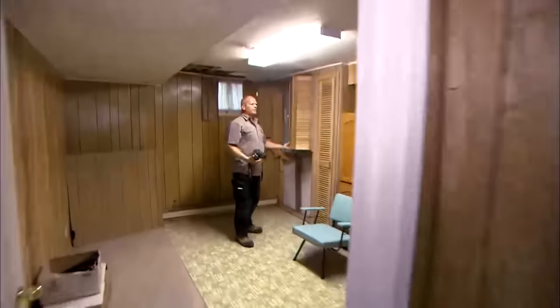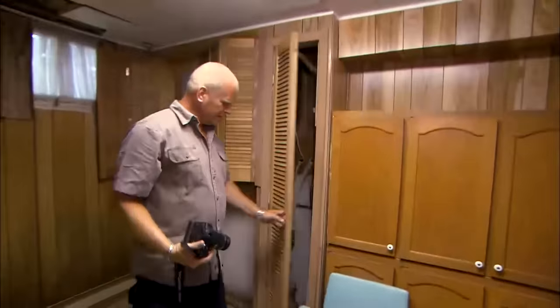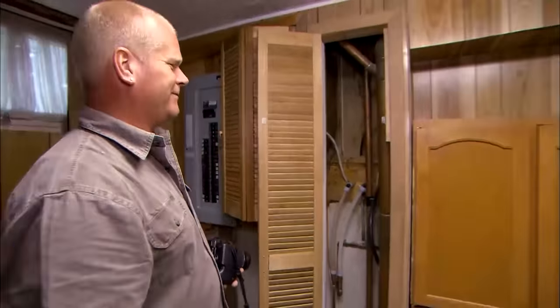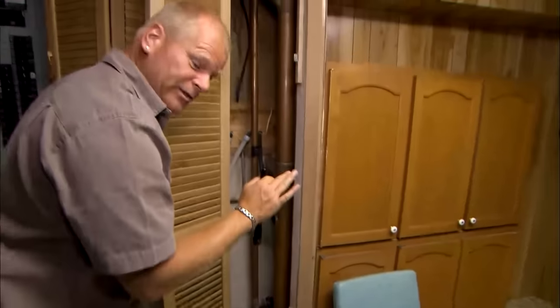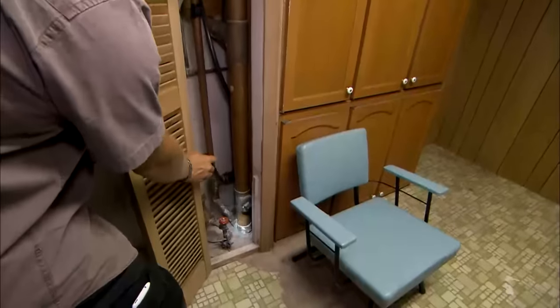From a nice built house to someone who's come in and done some work. Look at this, this is the drip line from the furnace. They've trapped a drain in the vent line, which means you can actually do it, but this is methane gas coming out of here. There's no trapping that air from coming back right on the main sewage line, so it just allows all this to bleed back in.